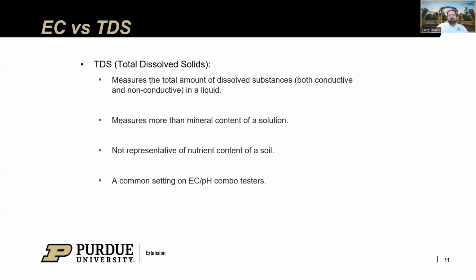I wanted to throw this in because when looking at meters, this is a term that you're going to come across. In our scenario, this isn't relevant. Total dissolved solids: if you get a combo probe that has pH and EC, it will also frequently have total dissolved solids. That measures the total amount of dissolved substances, both conductive and non-conductive, in a liquid. So we're measuring more than the mineral content of the solution, and that's not representative of the nutrient content of that soil. So that's not what we're looking for, but it is a frequent additional setting you'll find on those meters. It's just not one that we're going to be using. So you can ignore the TDS setting on these probes if you happen to come across it. Stick with EC if you are trying to get a snapshot of the mineral content of soil.